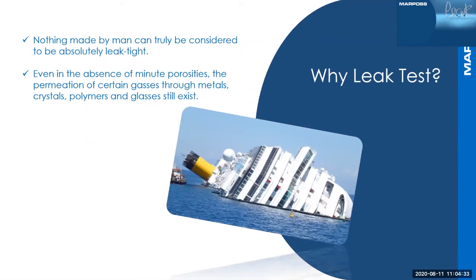Something to consider: everything leaks, it's just a matter of what scale we are using to measure. For automotive parts like an engine block or transmission case that contain oil or coolant, we normally see leak rates of less than 10 cc's a minute of air, which will prevent puddles of oil and water from accumulating on your garage floor. Even nuclear waste containers are tested for leakage. While that leakage specification is much tighter than what is seen on medical devices, we know that those containers are eventually going to leak. It's just a matter of how much over what time period.